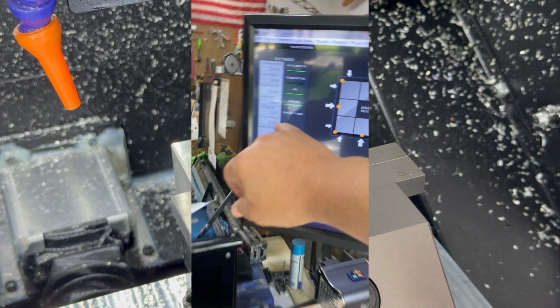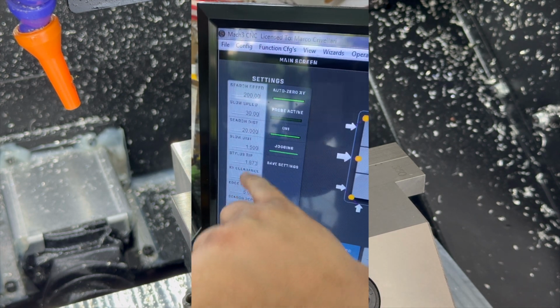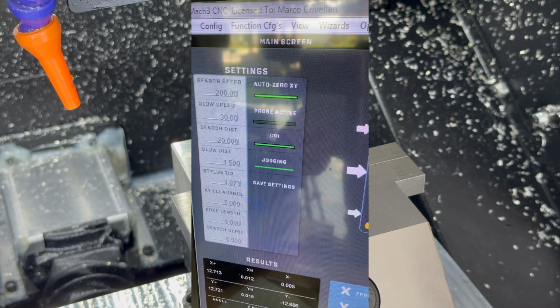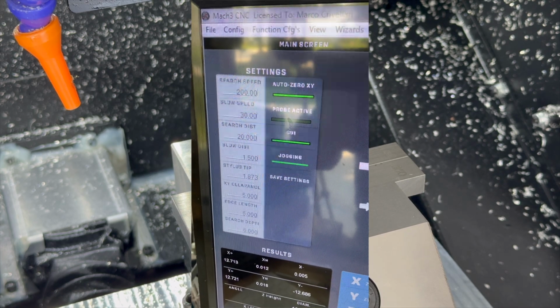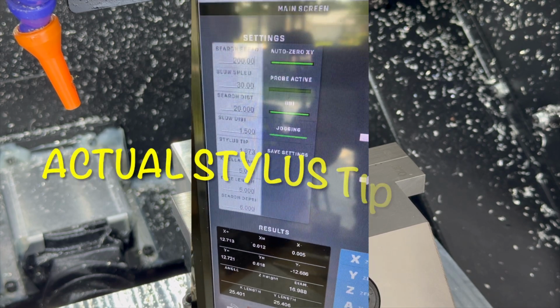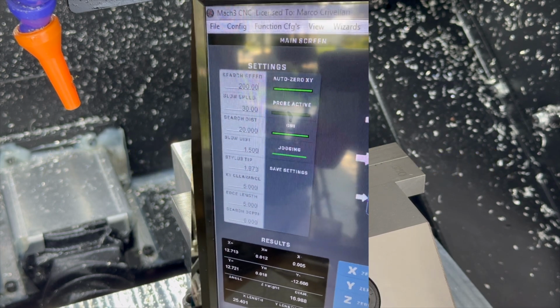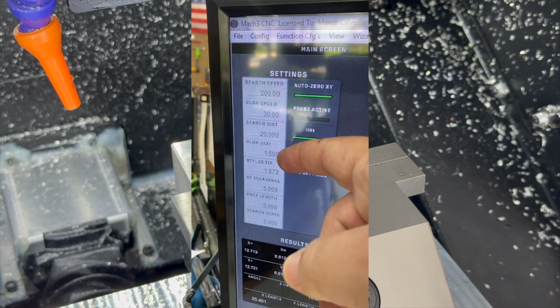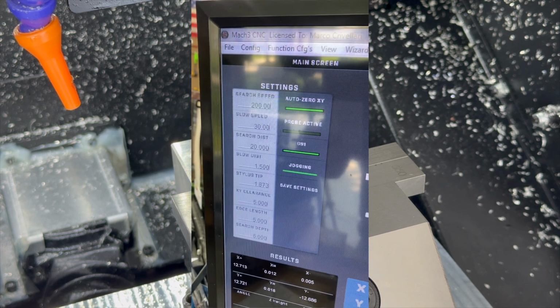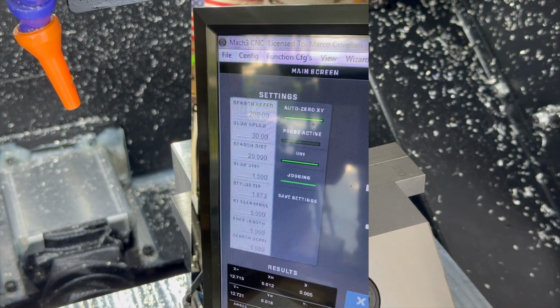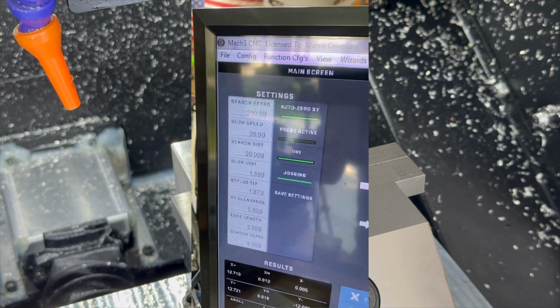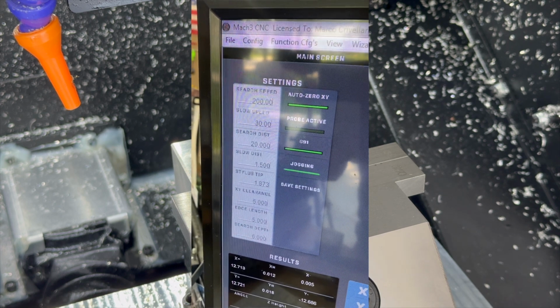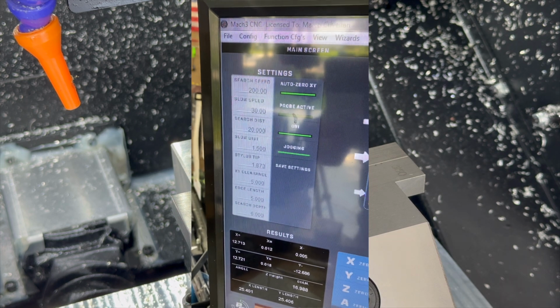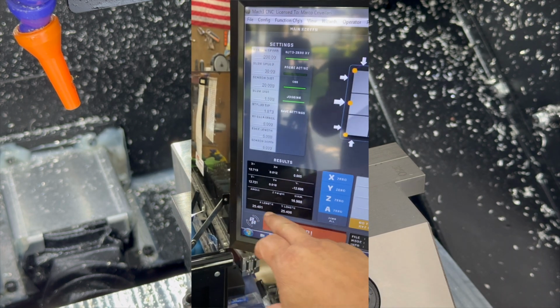And then, as you can see, the stylus tip is not 2 millimeters, it's actually a little bit less to compensate for the over travel. I figure that 1.873 works well with 200 millimeter per minute, and a slow speed of 30, to pretty much give me some good numbers.